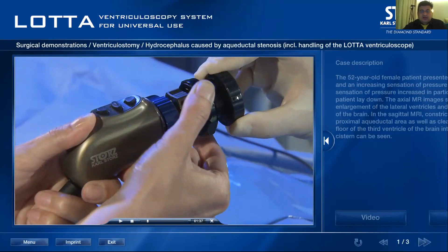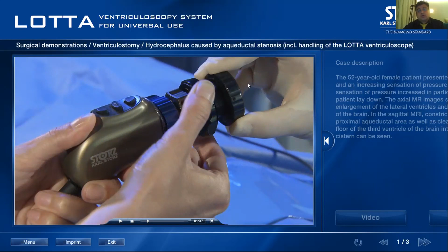The HD video camera is connected to a sterile optical adapter. Now this is a very important optical adapter because there are 2 types of camera heads. This particular camera head which the surgeon is holding is a non-autoclavable camera head. There is another variety, an autoclavable camera head, which can be autoclaved along with the cable at 134 degrees centigrade, 5 to 8 minutes, 3 atmospheric pressure. So if you use that autoclavable one, you need not use the adapter. Now why we are using it, the video will tell you.